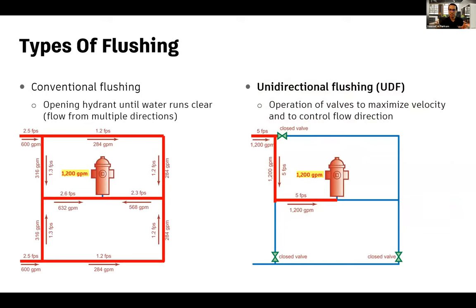Today we're going to put flushing into two categories: conventional and unidirectional. With conventional flushing, you open a hydrant and keep it open until the water runs clear. Flow comes in through various pipes in your distribution system and velocities are rather low — maybe one to two, maybe two and a half feet per second max, depending on your pipe diameters.